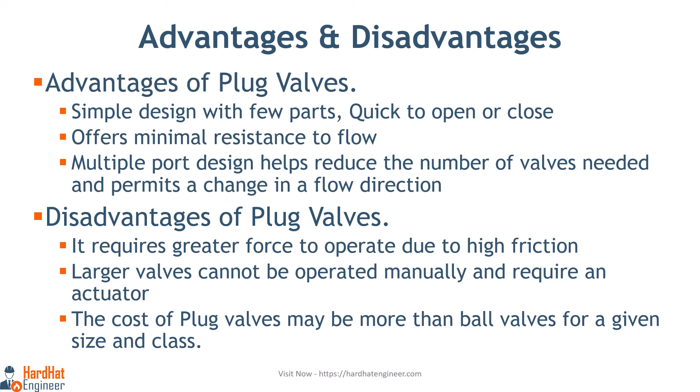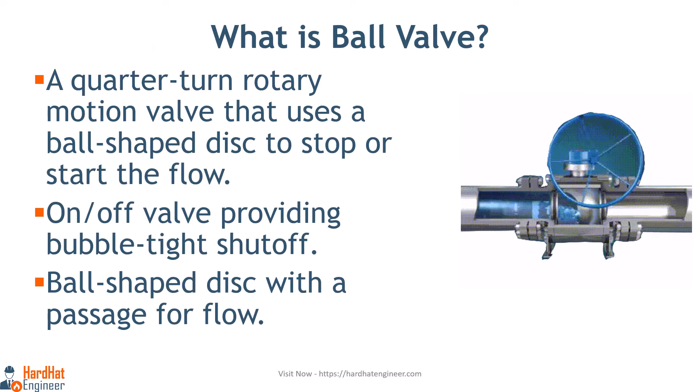Advantages of plug valve: simple design with few parts, quick to open or close, offers minimal resistance to flow, and multiple port design helps reduce the number of valves needed and permits a change in flow direction. Disadvantages: it requires greater force to operate due to high friction, larger valves cannot be operated manually and require an actuator, and the cost may be more than ball valves for a given size and class.